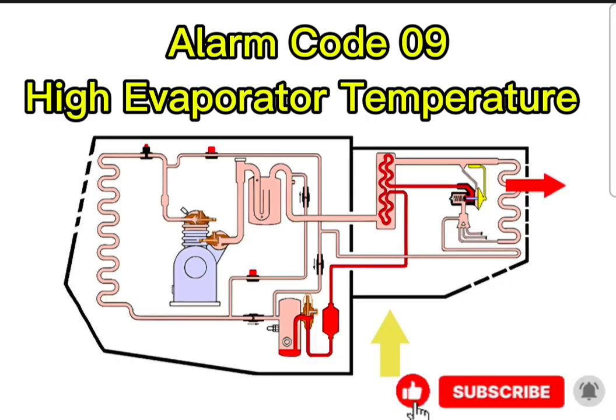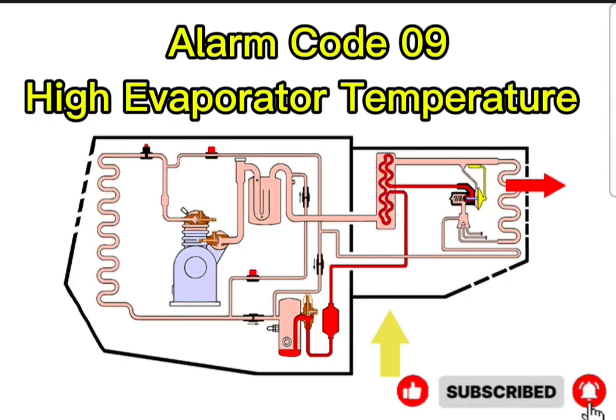And the refrigeration unit's logic board is doing the exact same calculus. Wow. It knows the coils need to be defrosted, but it has lost its eyes. So it says, I'm just going to blast the hot gas bypass for 15 minutes straight because historically that usually melts the ice. Right. But because it can't verify the environment, it overshoots the mark, cooks the internal components to 155 degrees, and forces that ungraded shutdown sensor to step in as the absolute last line of defense to save the machine's life. It's a programmed fallback protocol that actively damages the unit. It chooses the risk of catastrophic overheating over the certainty of freezing solid.